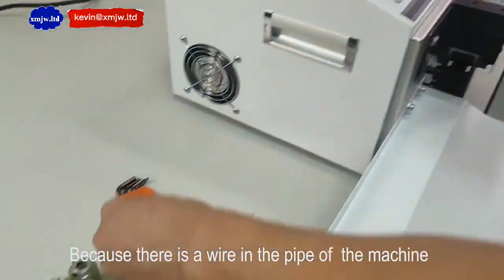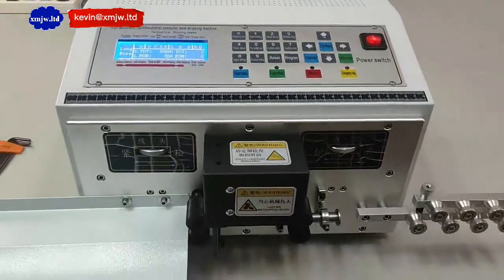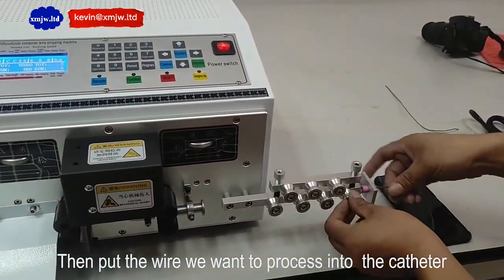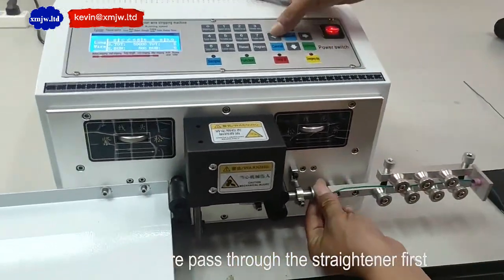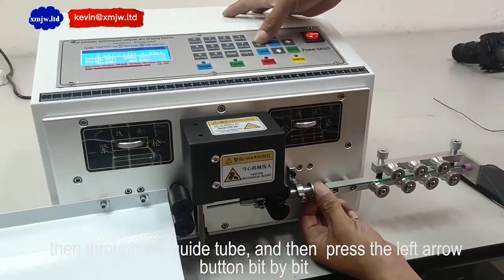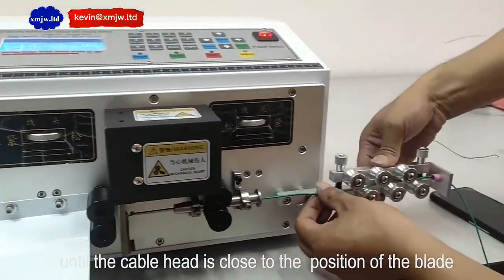Because there is a wire in the pipe of the machine, press the right arrow button for a while to return this wire. Then put the wire we want to process into the catheter. Let the wire pass through the straightener first, then through the guide tube. Then press the left arrow button bit by bit until the cable head is close to the position of the blade.